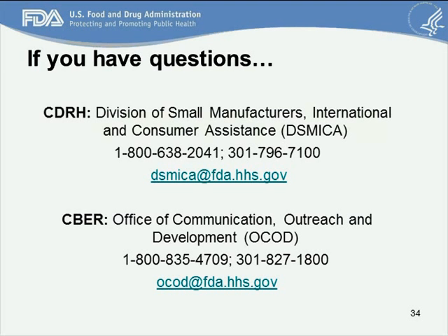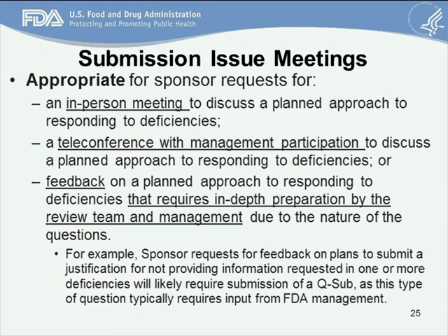If there's some question about, say, some additional testing that the agency is asking for, and we request a meeting to discuss that deficiency, and the 510K is on hold, if that meeting doesn't occur until 90 days or later into the process, you only have 180 days on hold, and then you might not have enough time to do the testing that's requested. So was that brought up in the comments at all, or is that something that FDA has considered?